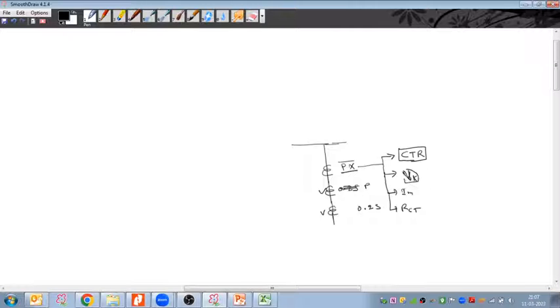And now we are discussing the knee point voltage calculations. For this, we have already done one session on what the knee point is and the basics of the knee point calculations. All this we have discussed. We have seen the knee point voltage requirement and the formula as per the IEC also. We have also seen that if we need to use a P class CT core for any unit protection or any zone protection, how we can calculate the knee point voltage for a P class CT.